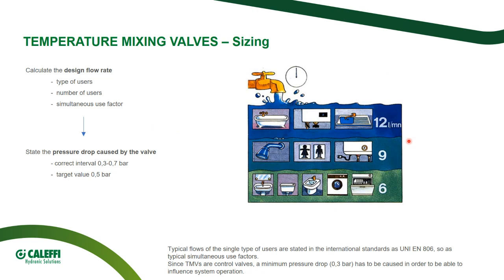The second crucial question is how big my valve has to be. The sizing process is crucial for the thermostatic mixing valve or digital mixing valve because it will ensure and grant the stability and the accuracy of the regulation. So first of all, we have to calculate the design flow rate. The design flow rate depends on the type of user, the number of users, and also on the simultaneous use factor. That is a probability. This probability is related to the nature of the building: a hotel, a hospital, an airport, a school, or a private dwelling have different simultaneous use factors. So there are some tables that explain it.